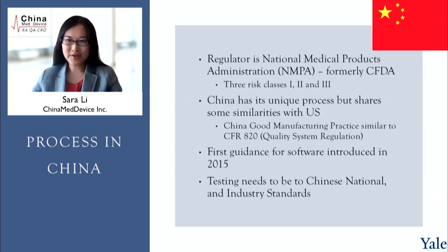There are 3 risk classes, Class 1, Class 2, and Class 3. Something unique to China, the clinical pathway does not depend on classification. If devices are not on an NMPA clinical trial exemption catalog, they will either need a comprehensive comparison to an equivalent device or undergo a clinical trial to meet regulatory expectation.